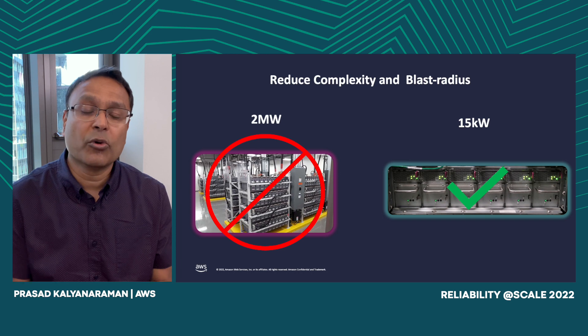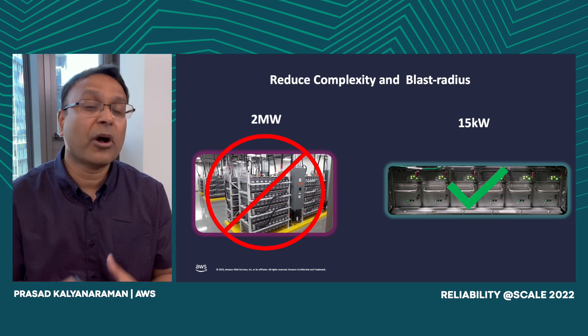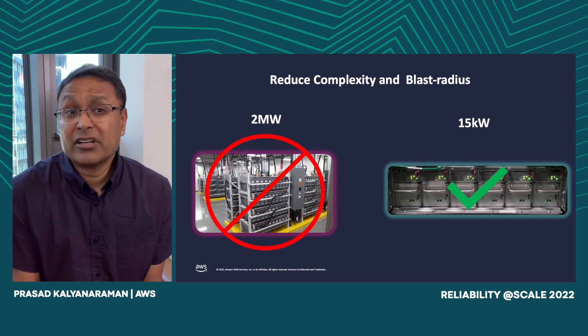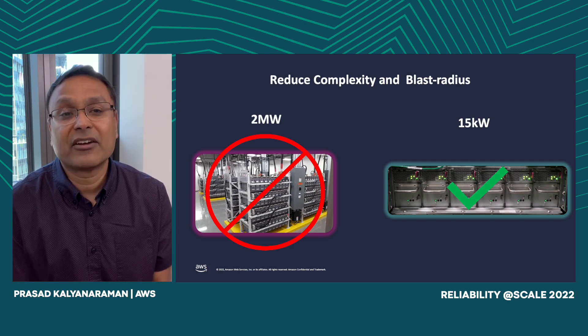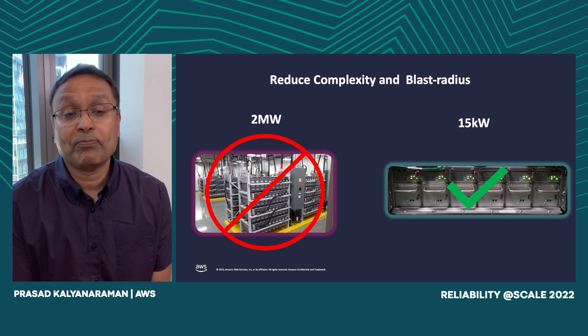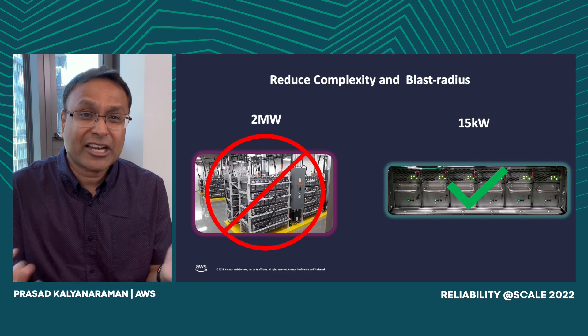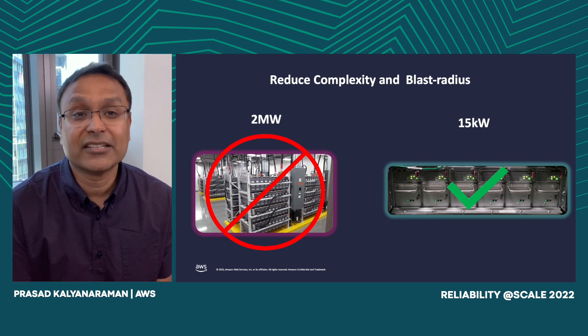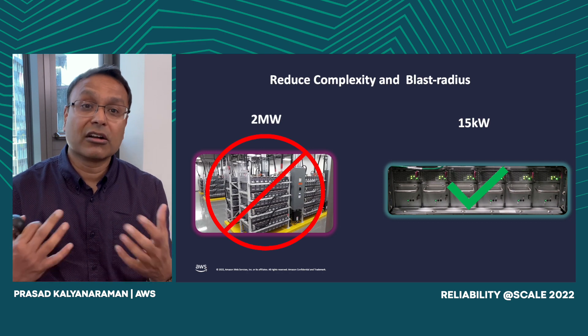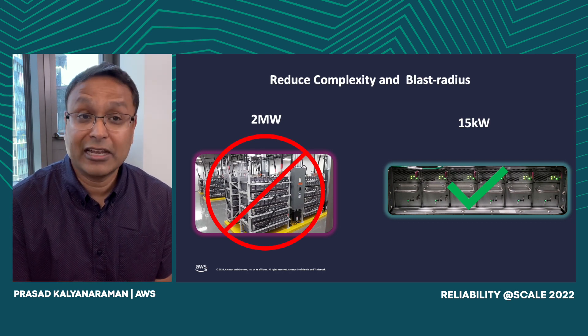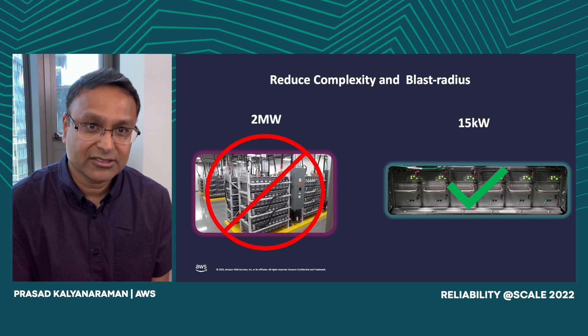We changed the design over time to reduce our blast radius from any kind of power event to literally 15 kilowatts — meaning a single rack which has battery backup power inside it. In addition to reducing blast radius, this also reduces complexity, since some of the harder things in electrical power design involve making sure you understand UPS operations.